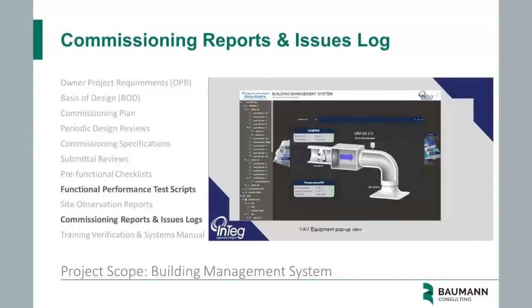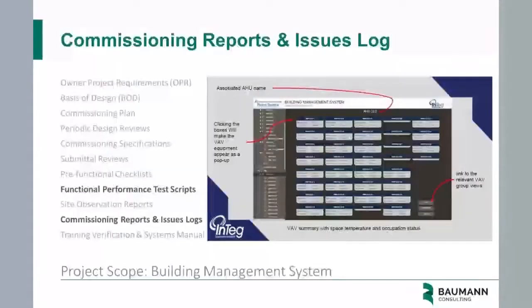So things to track. But things that the VAV would show us is anything to do with space temperature, zone occupancy statuses, and quick information on hot and cold zones very quickly, which this particular page here would show you. So basically this is for AHU G2.2, and this has a lot of VAVs attached to it.